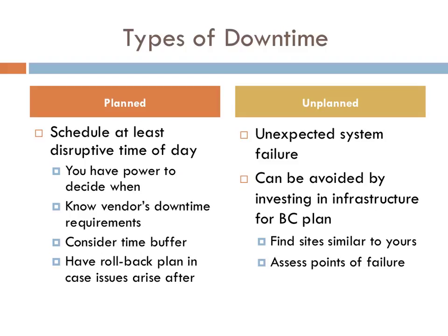And remember, if you are one of the first sites purchasing the product, then you are essentially the guinea pig, and there will be no mentor to ask in order to help you with downtime expectations. You should assess every possible single point of failure that could occur on the system. The more critical the function, the higher the priority must be to create redundancy.